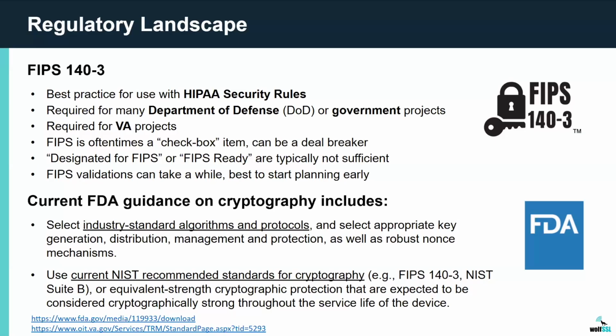Current FDA guidance, as outlined in previously mentioned documents, recommends selecting industry standard algorithms and protocols, ensuring appropriate key generation, distribution, management, and protection, and implementing robust nonce mechanisms. This emphasizes the importance of utilizing modern industry standard protocols over outdated or vulnerable legacy options. The guidance specifies the use of current NIST recommended cryptographic standards such as FIPS 140-3 or NSA Suite B or equivalent strength cryptographic protection. This is where FIPS plays a crucial role in the FDA guidance.